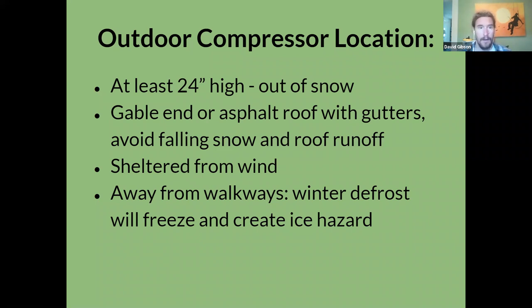That's fine too. But, you know, it's a fairly sophisticated unit. And while they're designed to be outside in all weather, they're not really designed to have 12 or 18 inches of snow slide off your roof on top of it. And then it's also recommended for them to be sheltered from the wind. And if you're on an island that's open and exposed to the ocean on one side, or if you were, you know, our house is in a giant open field until the windbreak we planted 2 years ago grows up taller. And so having it be sheltered from the wind will improve the efficiency of the unit in the wintertime. If the fan has to fight a 40 mile an hour wind, that's gonna cost efficiency for your system.